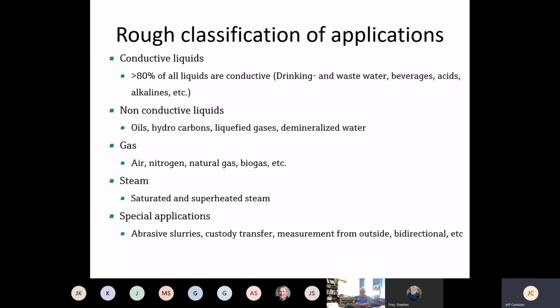So if we look at the applications that are out there, about 80% of all liquids are conductive. So that's a good thing, because magnetic flow meters can fill that void nicely. There's non-conductive liquids such as oils and hydrocarbons, DI water, liquefied gases. On the gas side, there's clean gases, inert gases, there's natural gas, there's wet, dirty gases like a biogas, gases coming off a digester. Obviously, there's steam, both saturated and superheated, that we need to measure. And then there's plenty of special applications.